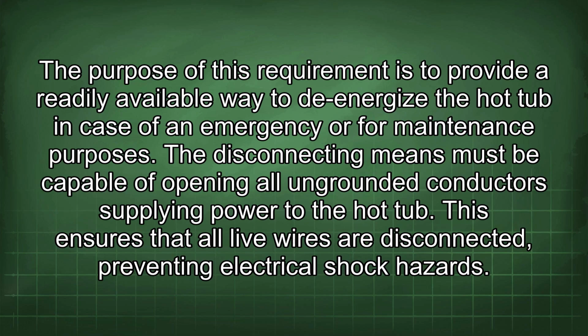The purpose of this requirement is to provide a readily available way to de-energize the hot tub in case of an emergency or for maintenance purposes. The disconnecting means must be capable of opening all ungrounded conductors supplying power to the hot tub. This ensures that all live wires are disconnected, preventing electrical shock hazards.